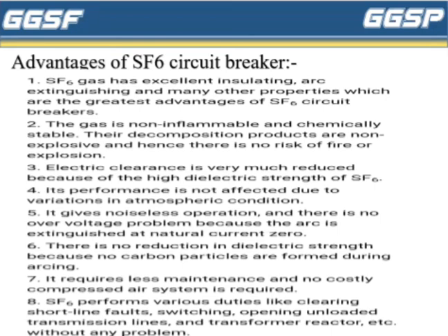Fifth, it gives noiseless operation and there is no overvoltage problem because the arc is extinguished at natural current zero. Sixth, there is no reduction in dielectric strength because no carbon particles are formed during the arcing. Seventh, it requires less maintenance and no costly compressed air system is required. Eighth, SF6 performs various duties like clearing short line faults, switching, opening unloaded transmission lines, and transformer reactors, etc. without any problem.